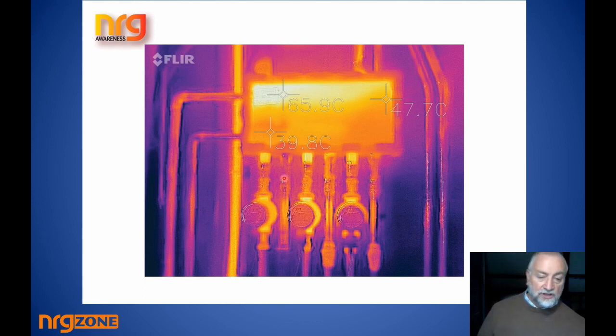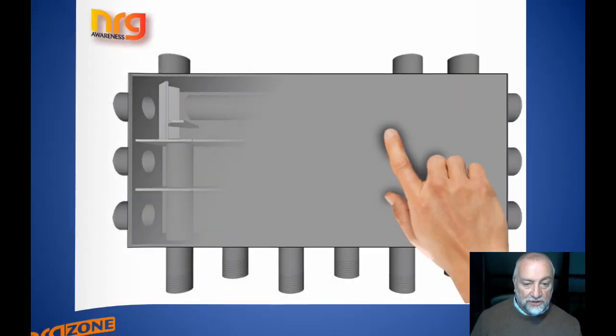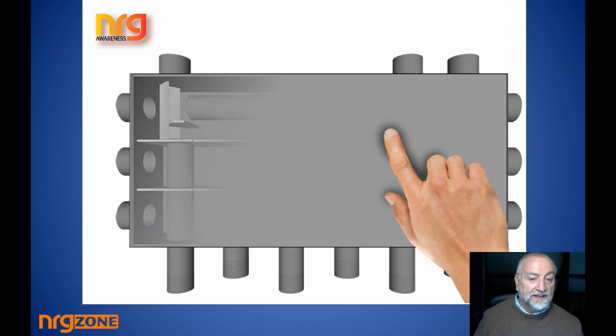We now can use our hands directly on the units, carefully obviously because it's above 60 degrees, and you can actually detect where the temperature is. By putting your fingertips carefully at the different surfaces, you can hold onto the flow and return pipe to a given zone or to the boiler, and you can check your differentials. Another very useful thing is one hand on the flow pipe coming in from your heating appliance, one on the flow going out to each zone. Are you getting the correct temperature out? If there's an issue, you'll find the difference. Your hands are incredibly accurate with regard to detecting even the slightest temperature difference sometimes.